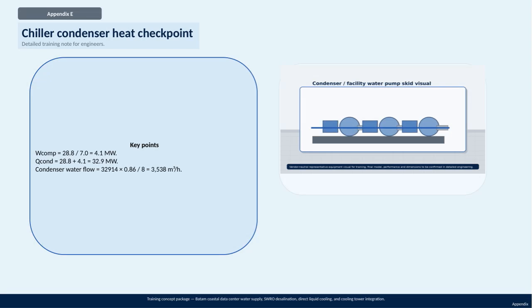Here in Appendix E, we have the chiller condenser heat checkpoint, which serves as a detailed training note specifically designed for engineers. This section is part of our broader training concept package focused on the Batam Coastal Data Center's water supply system, including SWRO desalination, direct liquid cooling, and the integration of cooling towers. Let's focus on the key points presented. First, the compressor work, Wcomp, is calculated by dividing 28.8 by 7.0, resulting in 4.1 megawatts.